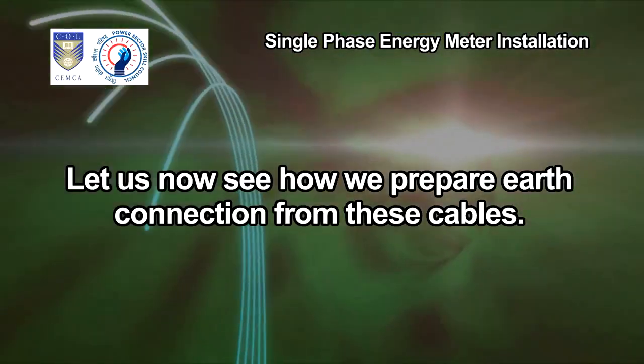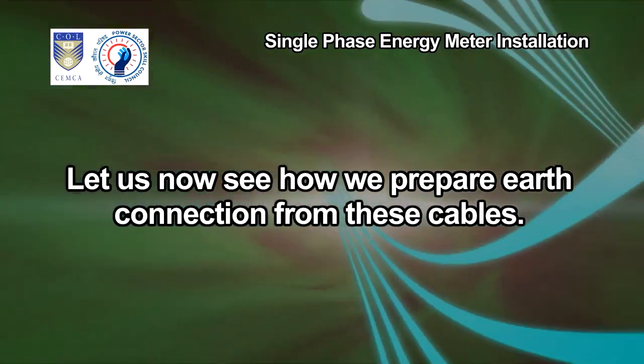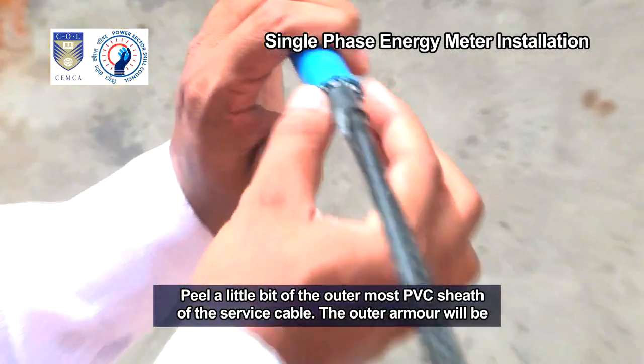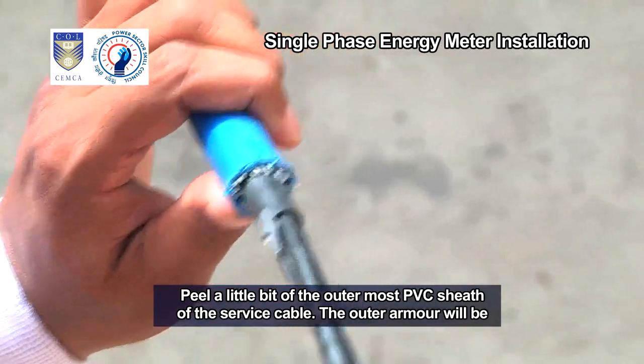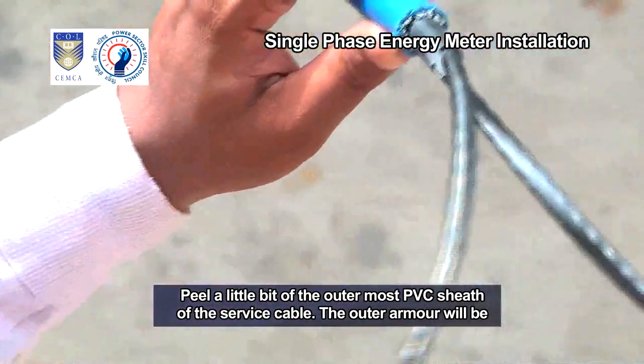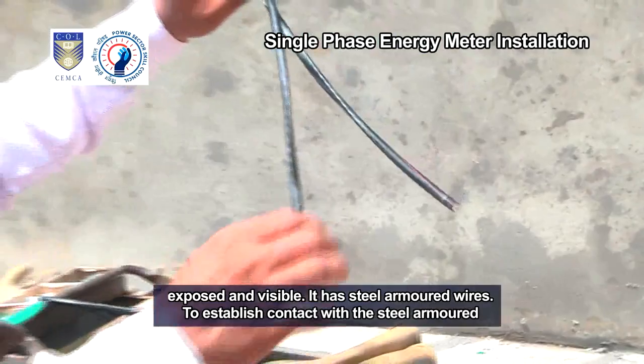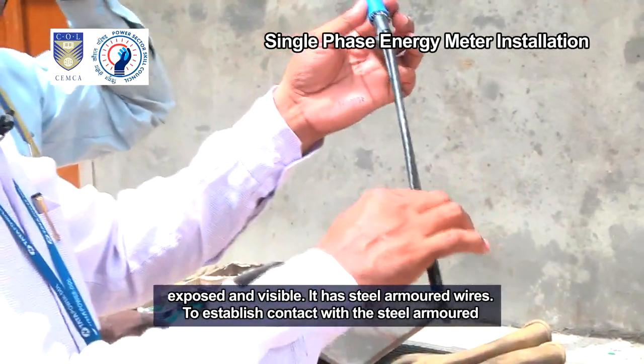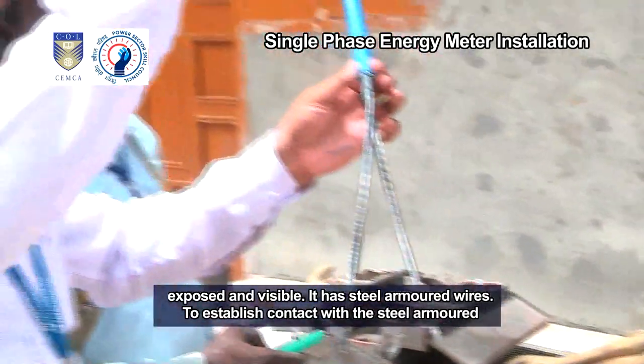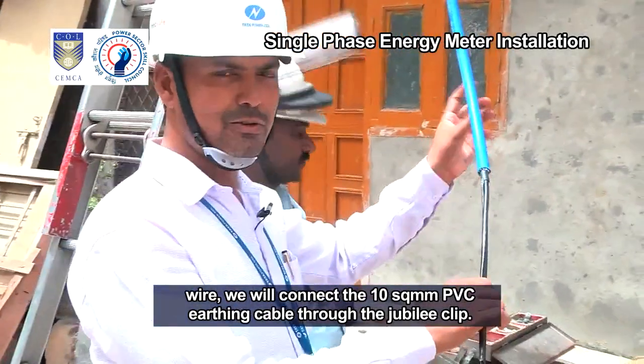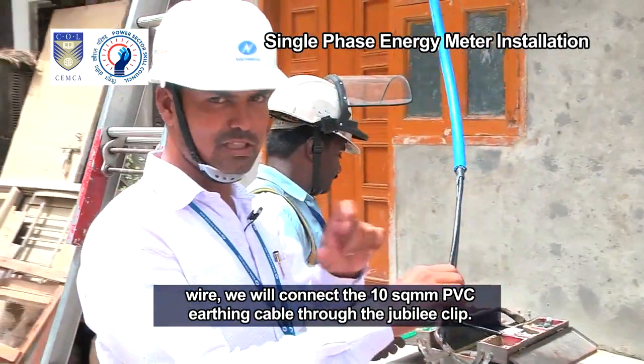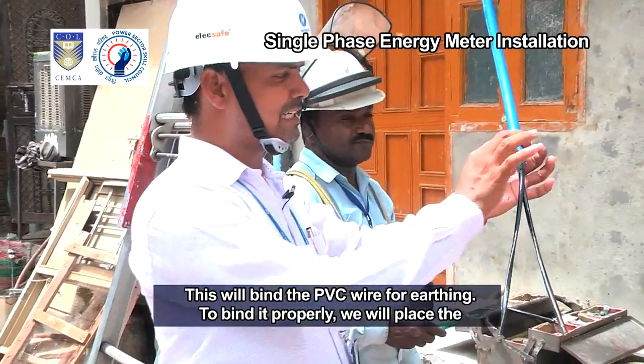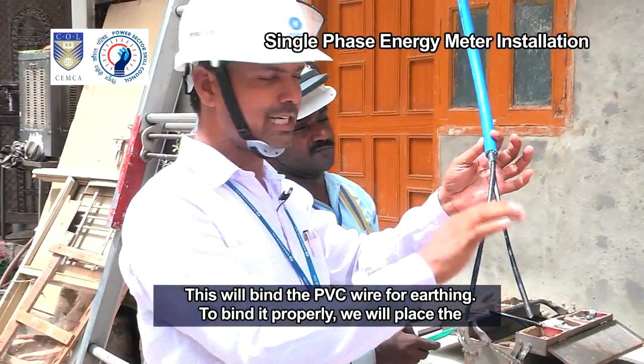Let us now see how we prepare the earth connection from these cables. Peel a little bit of the outermost PVC sheath of the service cable. The outer armor will be exposed and visible. It has steel armored wires. To establish contact with the steel armored wire, we will connect the 10 square mm PVC earthing cable through the jubilee clip. This will bind the PVC wire for earthing.